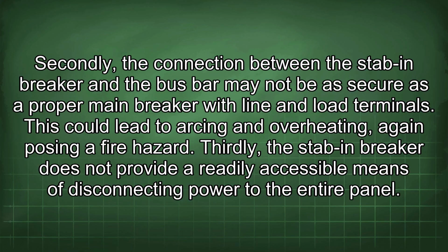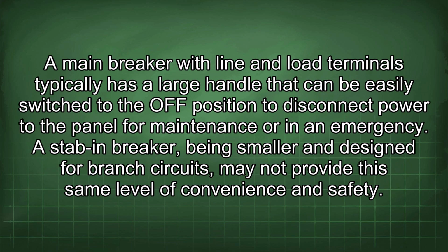Thirdly, the stab-in breaker does not provide a readily accessible means of disconnecting power to the entire panel. A main breaker with line and load terminals typically has a large handle that can be easily switched to the OFF position to disconnect power to the panel for maintenance or in an emergency. A stab-in breaker, being smaller and designed for branch circuits, may not provide the same level of convenience and safety.